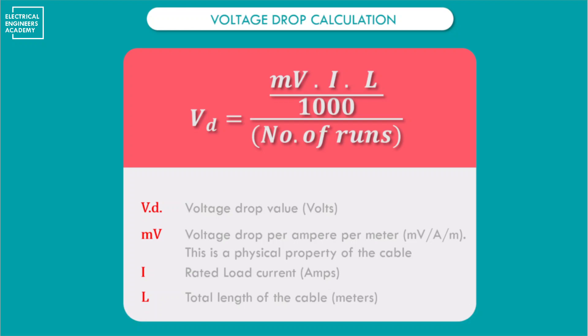As you recall, the voltage drop calculation formula consists of these factors, and finally we divide by the number of runs. So the number of runs is a very important deciding factor in the voltage drop calculation. You need to ensure that the correct number of runs is specified, otherwise many wrong decisions can be taken and it will have a drastic effect on the operation of your power distribution system.